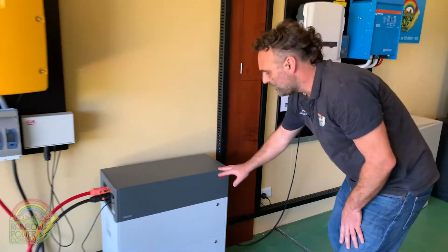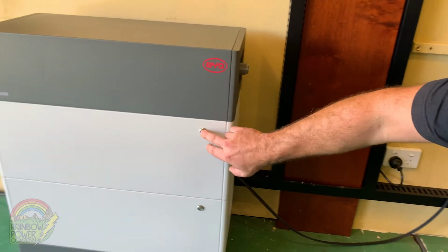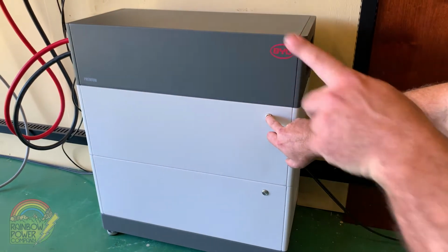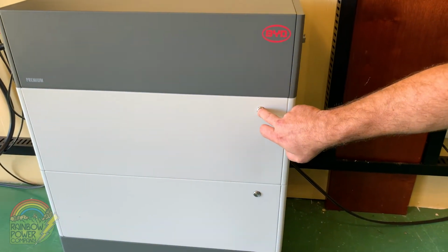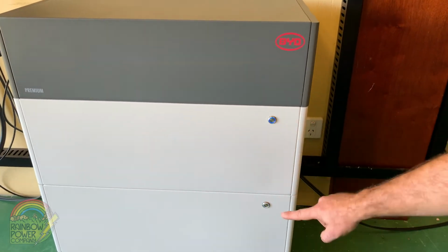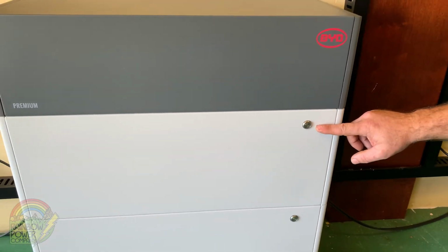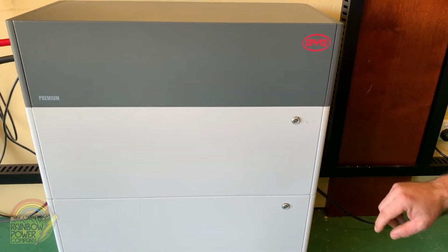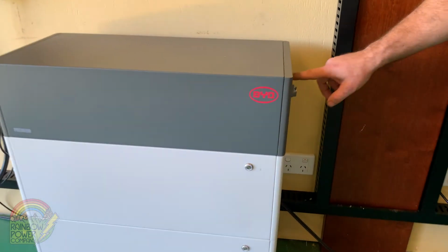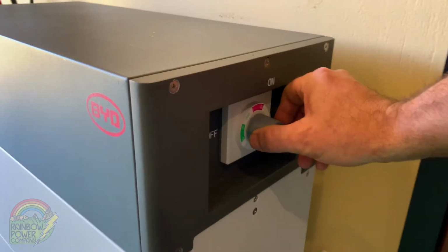To turn the battery on, we hold our finger on the battery button this time, not the BMU, until the lights come on. You can see how the lights are indicating here - it takes a few seconds to start up and become stable. Once the lights are blinking white, we know the battery is turned on. Again, around the corner, we need to turn the DC isolator into the on position.